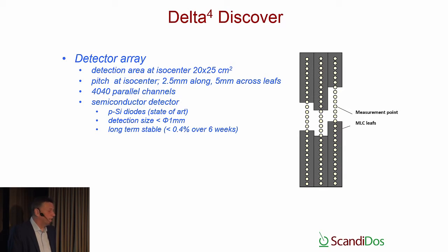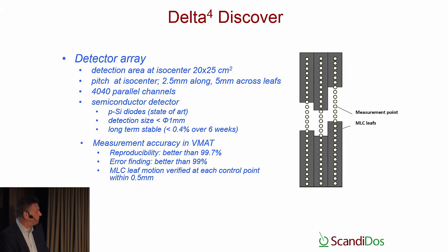It's less than 1% per 25 kilogray sensitivity decrease, and that means if you calibrate it in the beginning of a session for a patient, and the treatment is going on for 6 weeks, and all patients at the clinic are measured when they are treated, then the sensitivity change is less than 0.4% still. So it's extremely long-term stable.